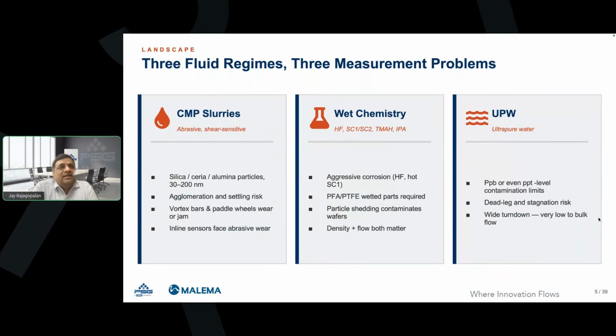But the risk here is agglomeration. If you're not correctly designing the flow meter or flow controller, and if the path of the fluid is not well managed, the slurry can lead to agglomeration and settling risks, which can create wafer defects. Because of those reasons, technologies such as paddle wheel, vortex flow meters, differential pressure flow meters or flow controllers are not really a choice. You have to go for an inline, but mostly non-obstructive type of product.